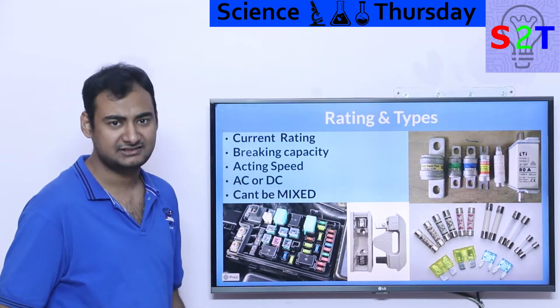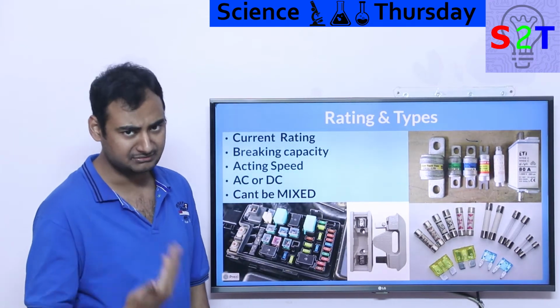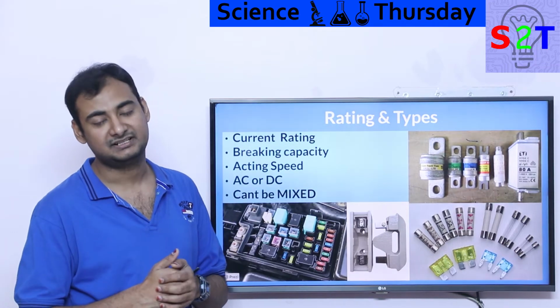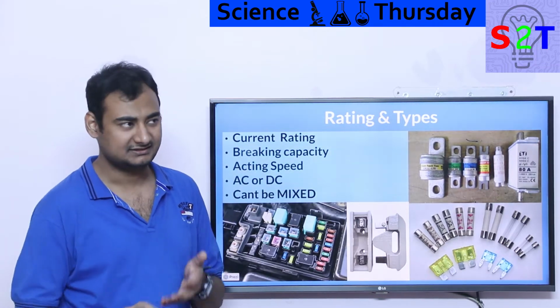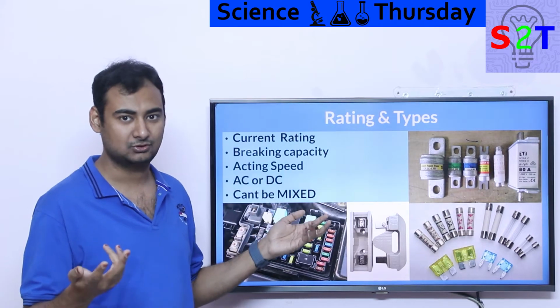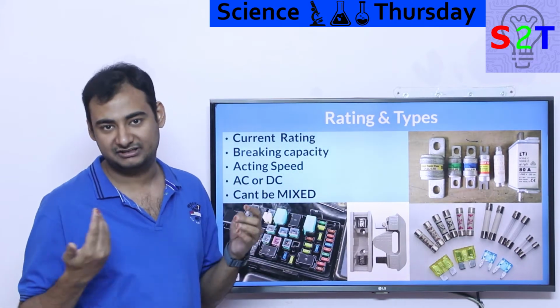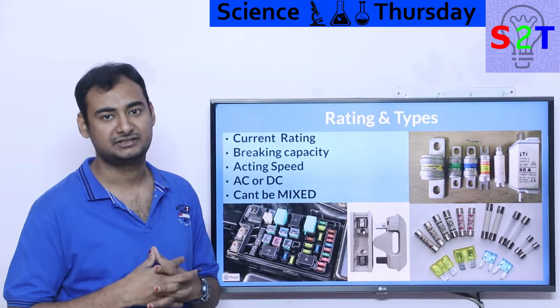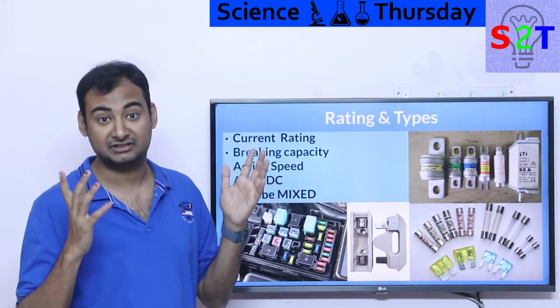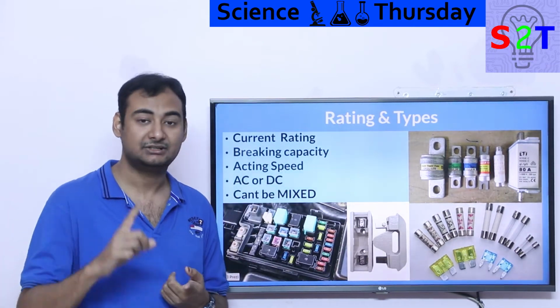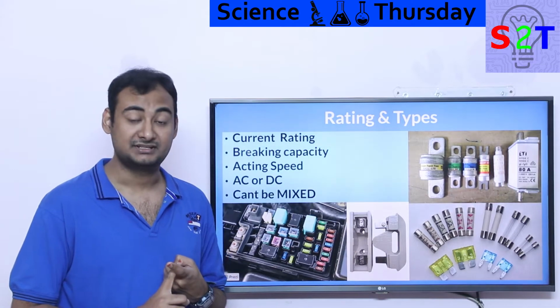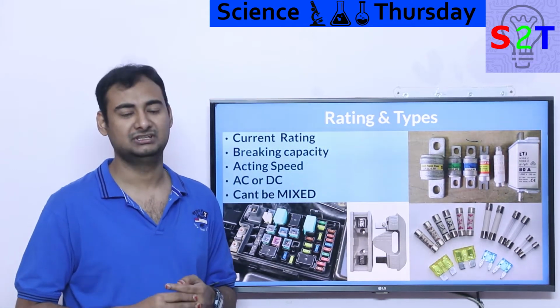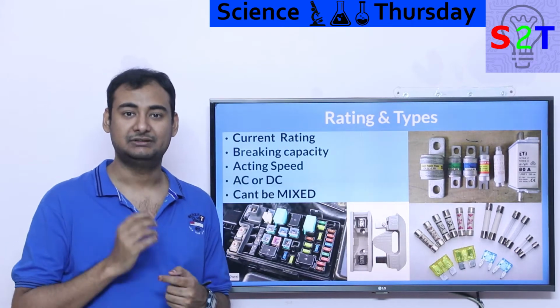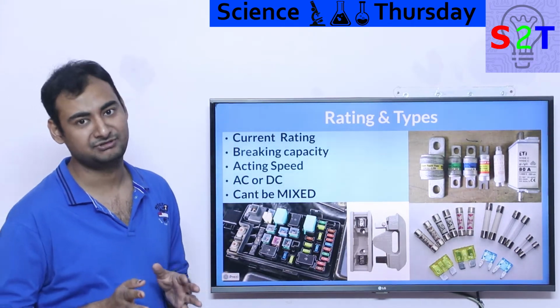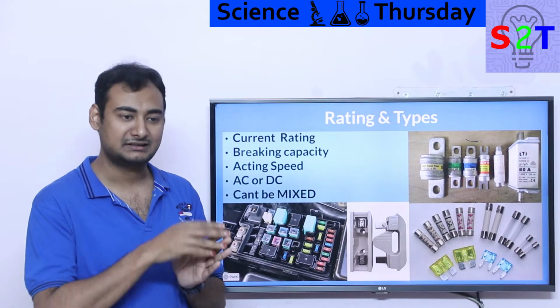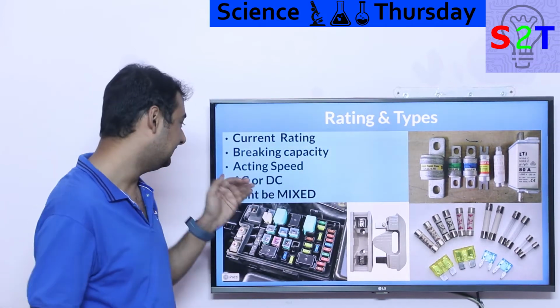Now that doesn't make sense, because the first thing you'd think is: if something bad happens and current is exceeded, deploy the brakes instantaneously. Why would you want acting speed to be slow? Simple reason: there are things that create a high current scenario the moment you turn them on. For example, anything with a giant transformer or coils in it, like motors, have huge inrush current, idiotically huge. If you have a sensitive fuse, it's going to blow every time you turn the motor on. So you need a fuse that lets that through, you need acting speed.